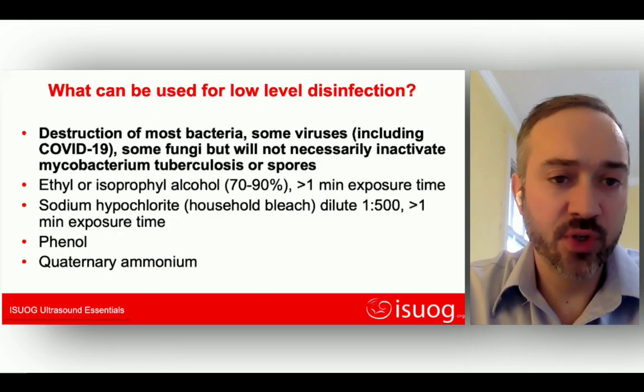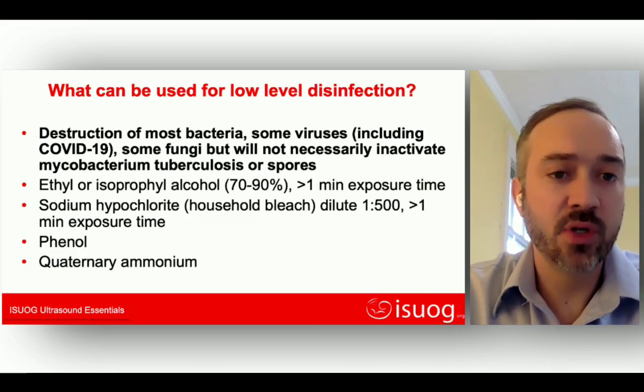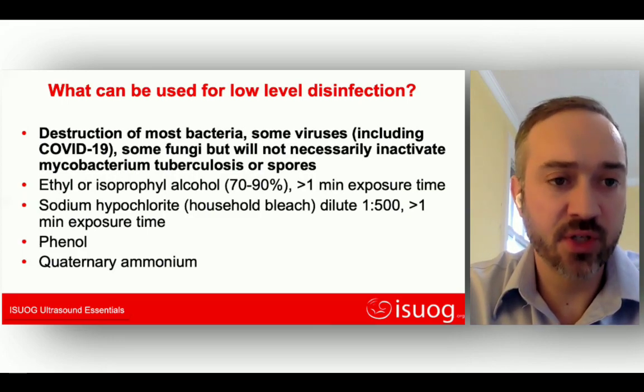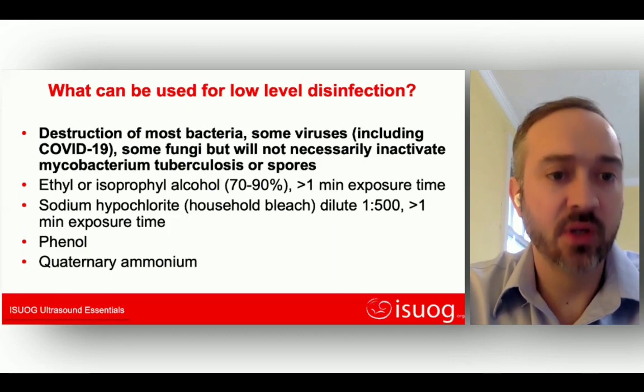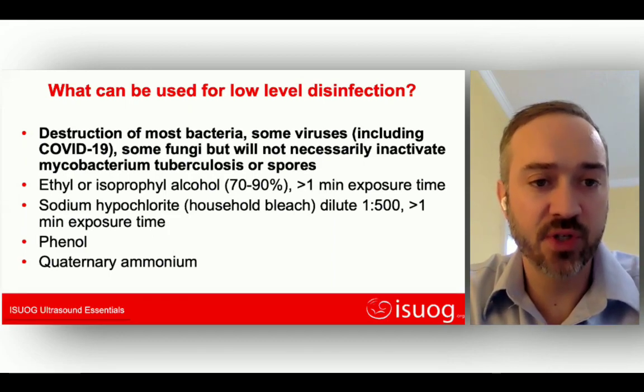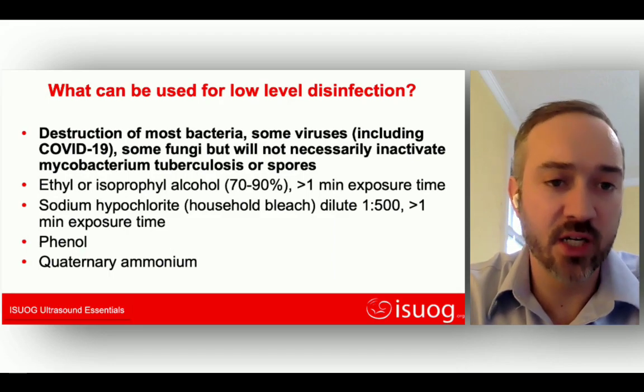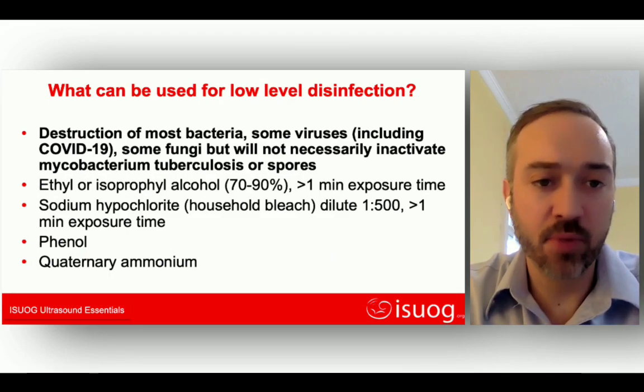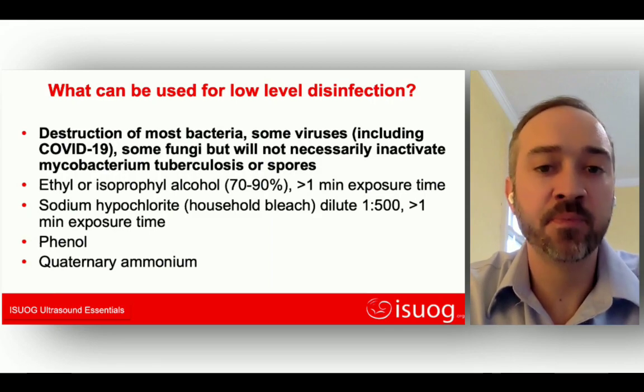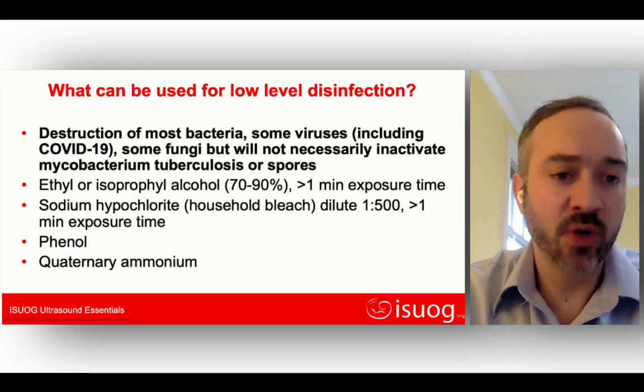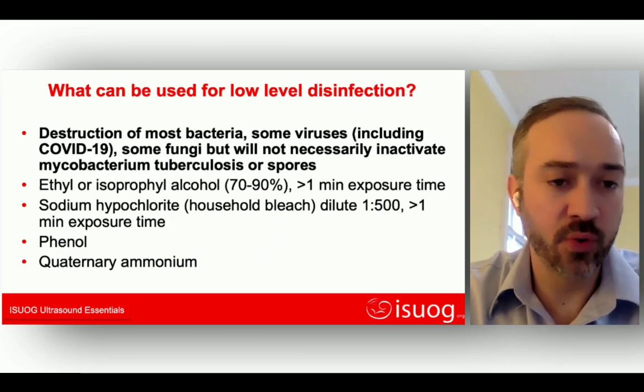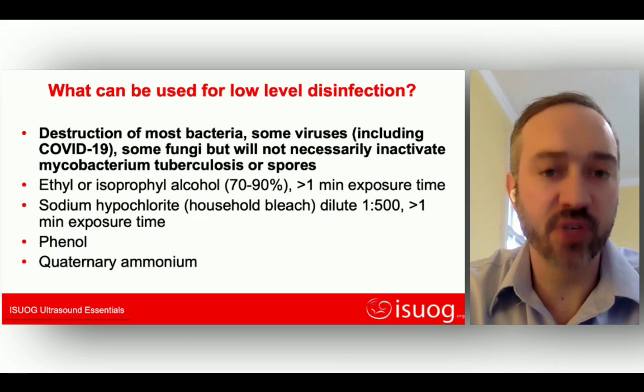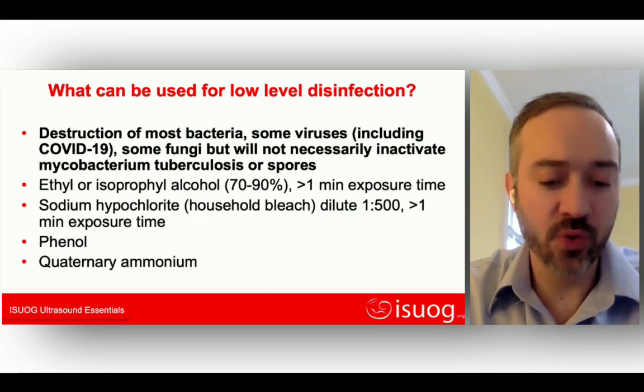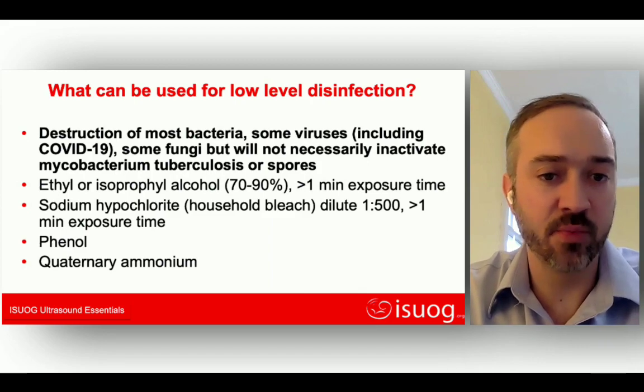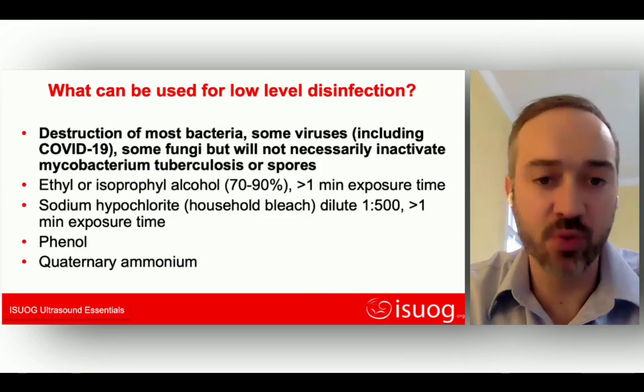So what can you use for high-level disinfection and what do you eliminate with it? So, low-level disinfection, I apologize. Low-level disinfection destroys most bacteria and some viruses, including COVID-19, but notably not HPV, and some fungi, but won't eliminate TB or spores. This can be done simply with alcohols, household bleach, or other common cleaning solutions with a relatively brief exposure time. So these would be like the wipes or methylated spirits that you use on your machines between patients on your abdominal probes.